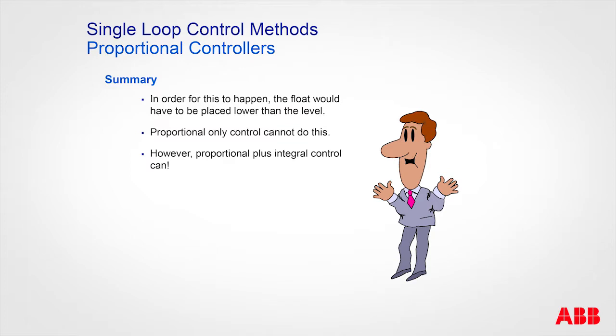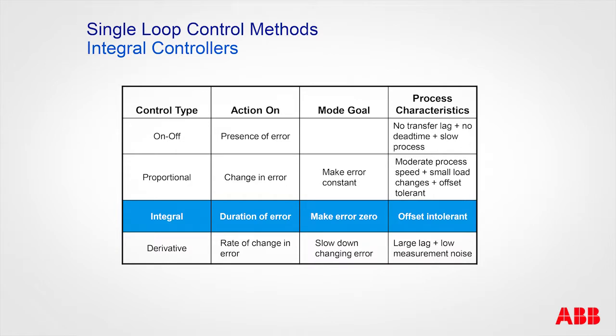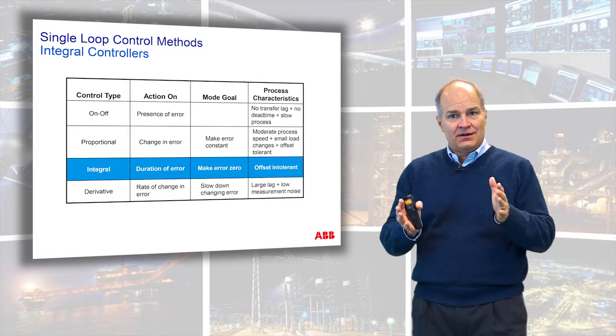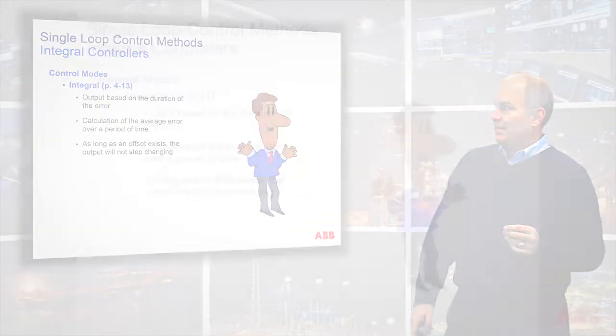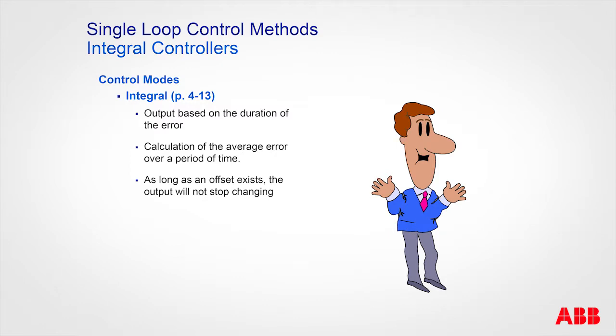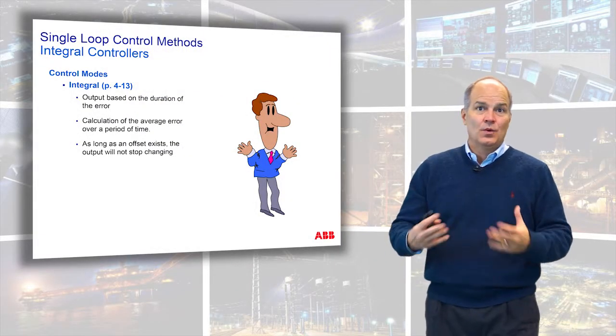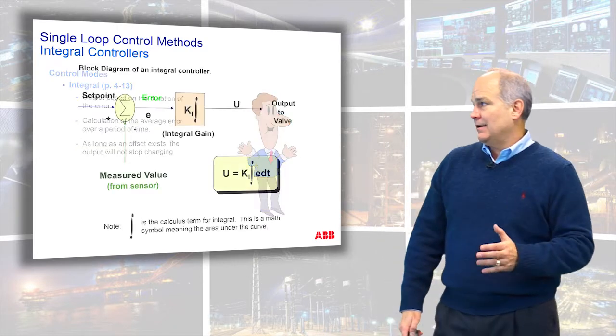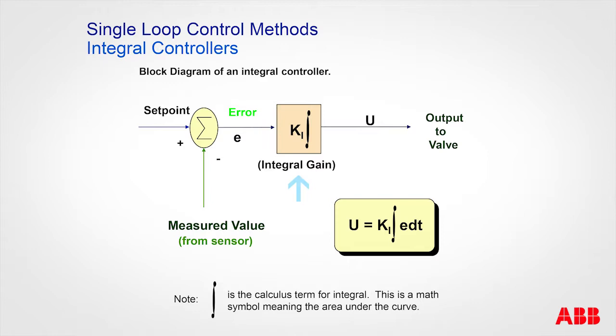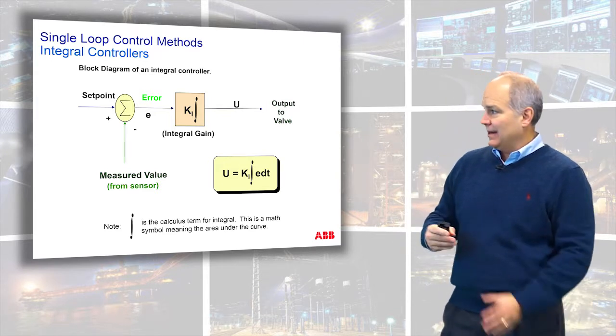On-off works on the presence of error; proportional works on the change in error but results in offset. Integral is next — it deals with the duration of the error and its goal is to make the error zero. The output is based on the duration of the error: it calculates the average error over a period of time. As long as an offset exists, the output will not stop changing. Another term for integral is reset. In a block diagram, the integral term calculates the area under the error curve over time, and the gain is simply a multiplier adjusting the slope.